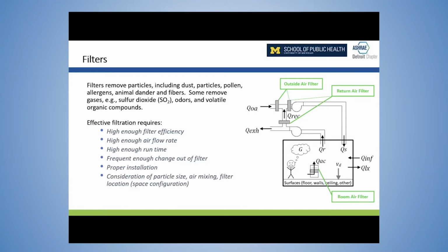To have effective filtration, you have to consider this as a system. You need a good enough filter with a high enough filter efficiency for those small particles. You need a high enough flow rate. You have to operate the system, so you need enough runtime. You have to maintain your filter and have changeout. The filter has to be installed without errors, without bypass. And you need to consider the configuration of the air mixing in the space and the sources within. So really, I'm again emphasizing the importance of considering the overall system.